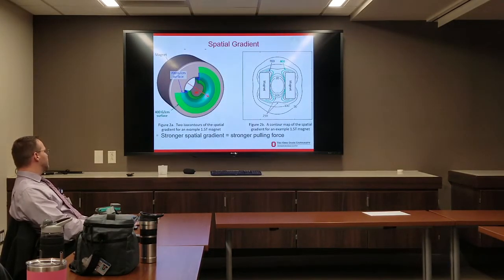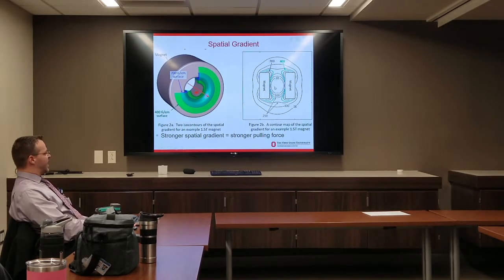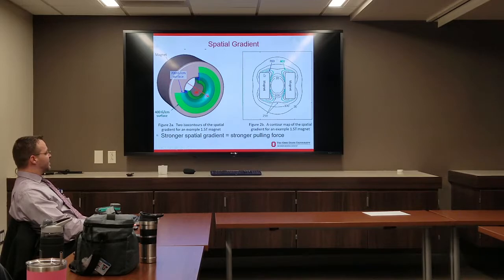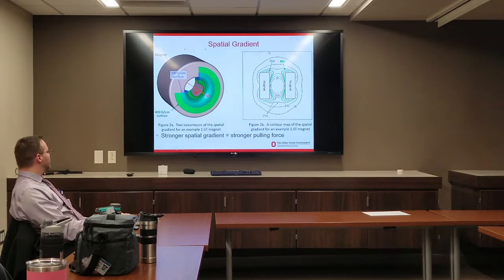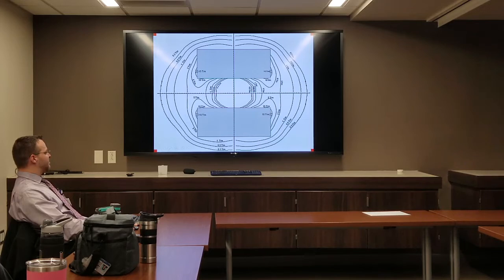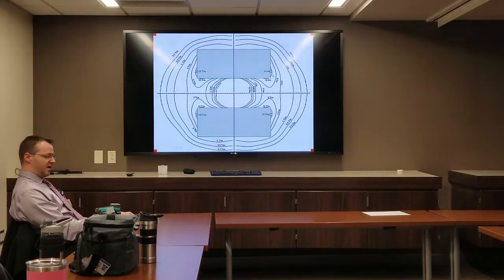Looking at a map of spatial gradients: at the center (isocenter) of the magnet, there is no spatial gradient, so there's no pulling force on an object there. Just outside the magnet, there's a strong force in that area, and the further away you get, that force gets weaker. The force is going to be strongest just outside the bore opening.